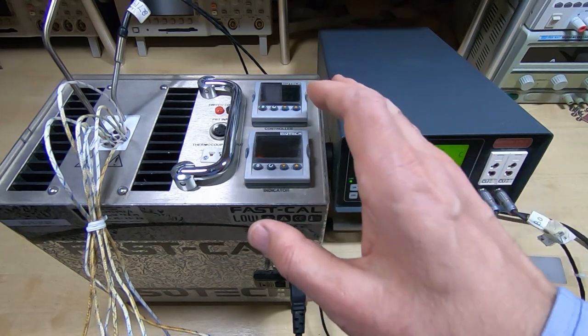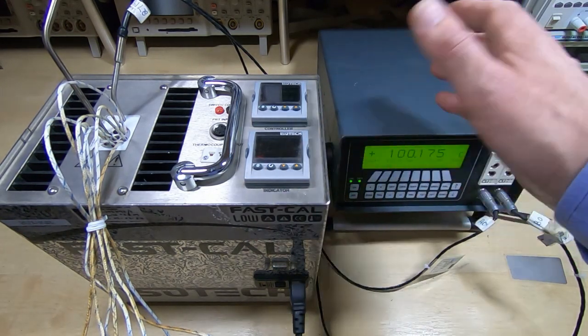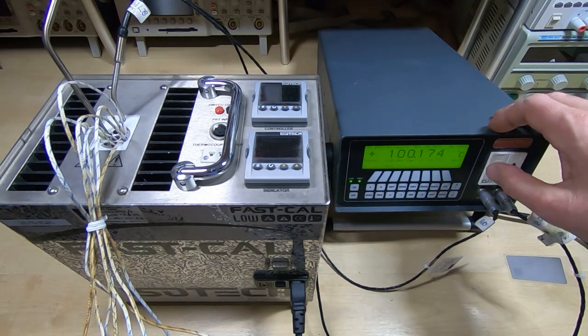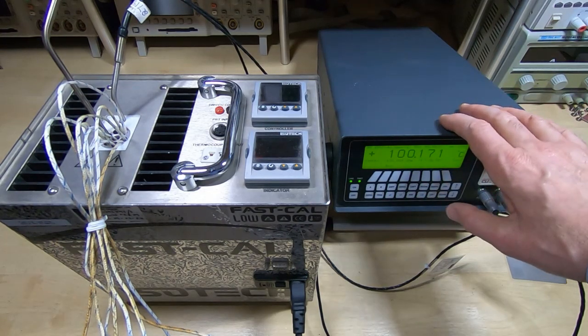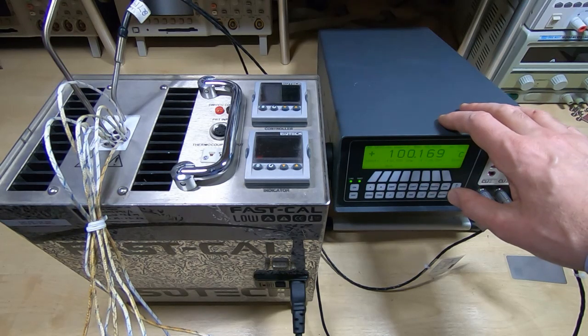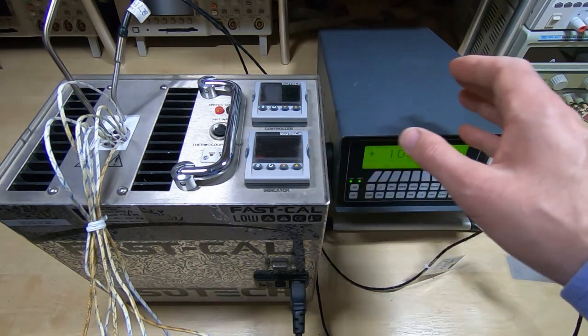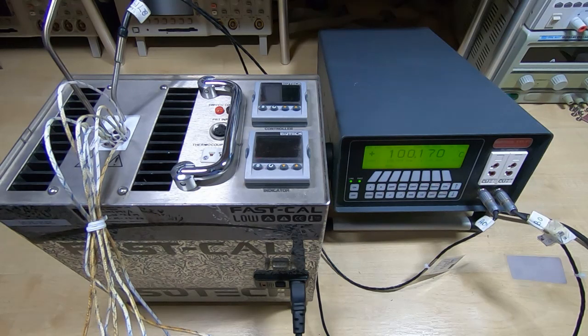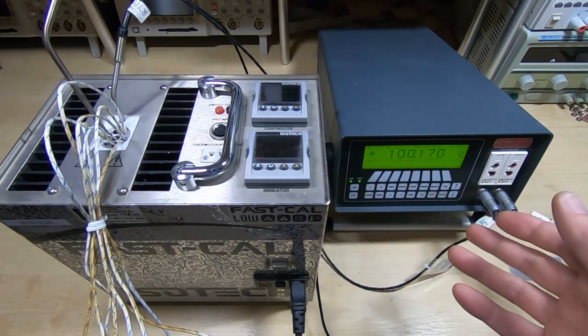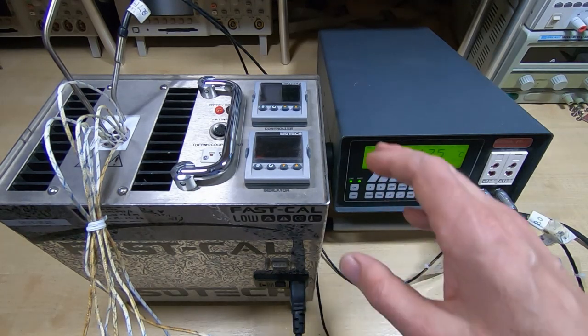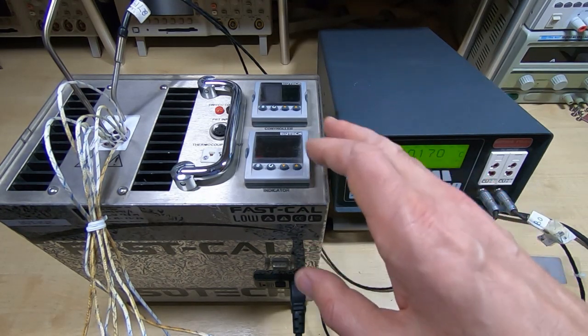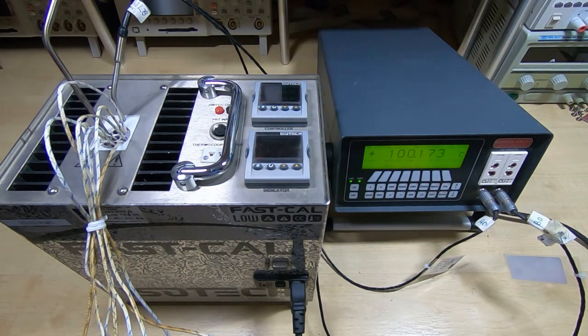So as I said, I didn't show it initially because you may have found this extremely boring, but this is the sort of thing you have to do before you start any in-depth investigation, and you have to repeat it periodically through the testing. You can't just do it once. At the very least, do it at the beginning and do it at the end. If the results at the end of the calibration period don't match what you had at the beginning, then obviously you need to review the testing that you've been doing, because there may well be some ambiguity in the data that you got.